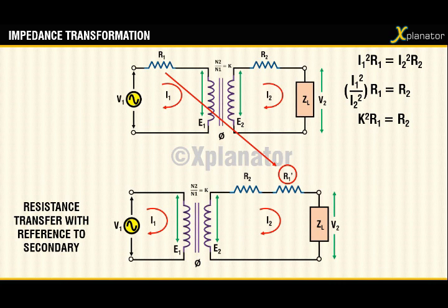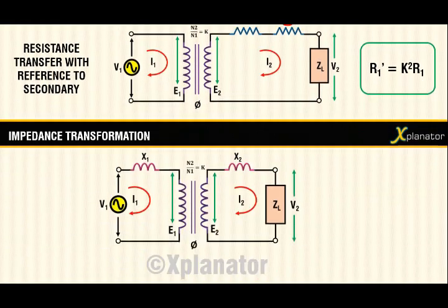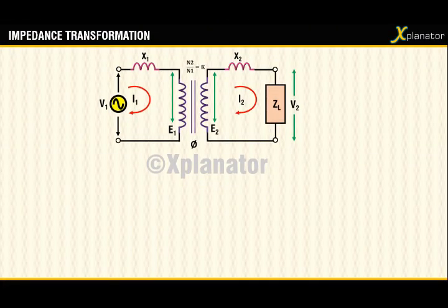The new resistance r1 dash will be equal to k² times r1. The same concept applies for reactance as well. If reactance transfer is desired, then the relation that is to be used is that inductance is directly proportional to the square of the number of turns.